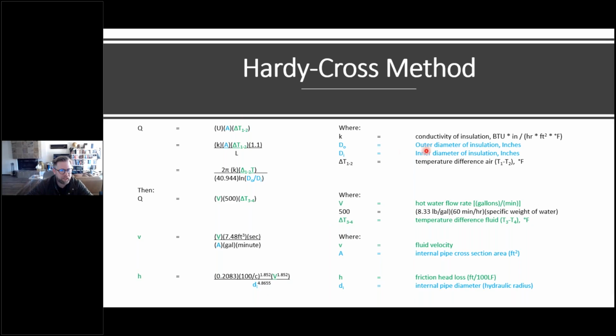Now, what I want you to pay attention to is these blue highlighted items, which in essence are one variable. It's all regarding the area of the pipe. We then have our volumetric flow rate, which is a second variable. We have our temperature differential of our fluid, which is a third variable. We have our velocity, which is based off of the volumetric flow rate and the area, which is a fourth variable.